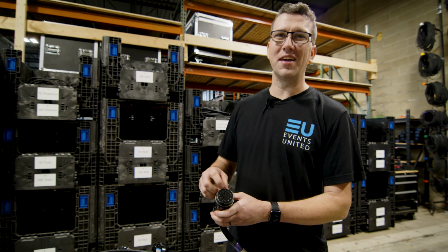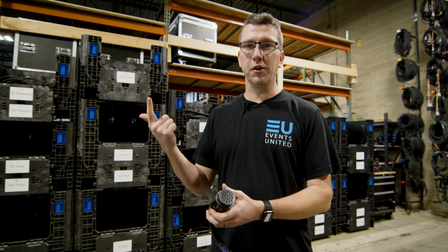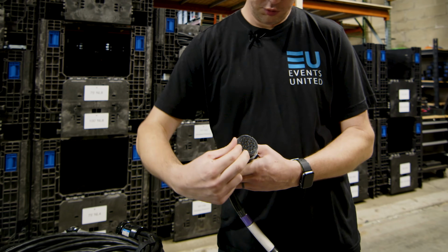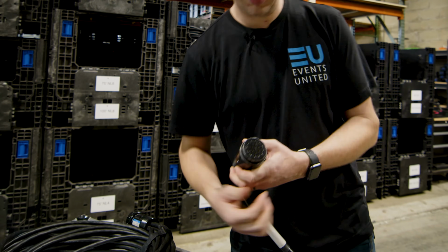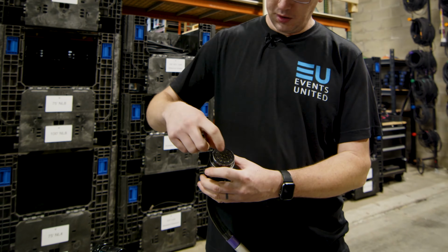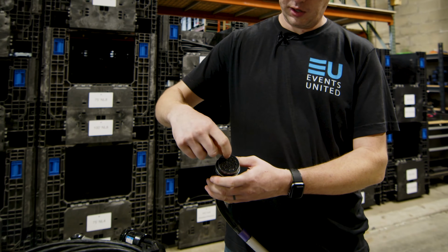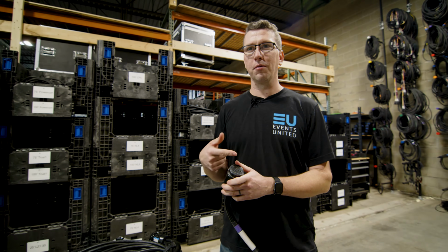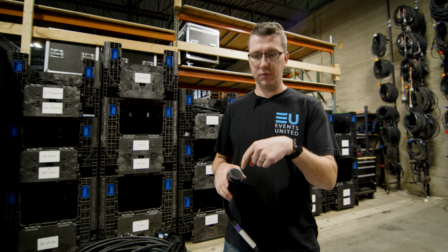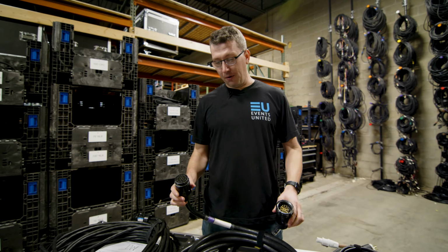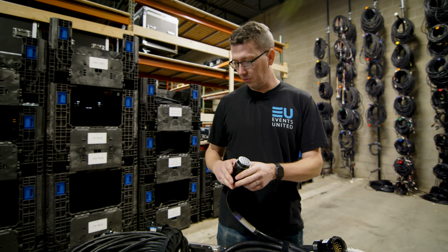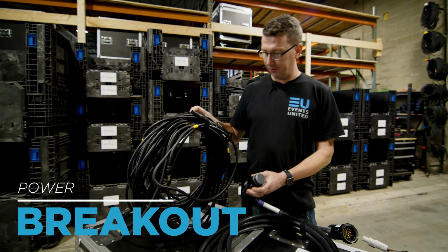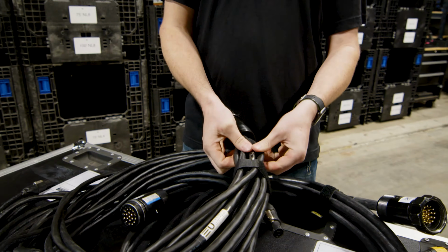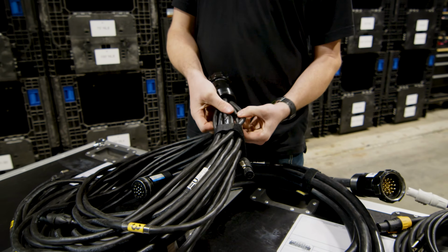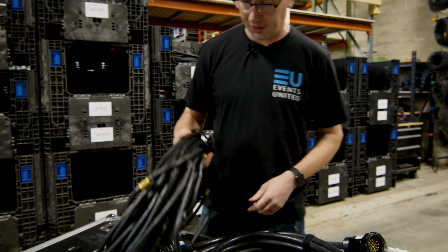Each one of these pins on the outer ring is a neutral and a hot. 1, 2, 3, 4, 5, 6 separate neutral and hot combinations. Then the center ring inside this connector joins all the pins, and the grounds get attached to those pins. But getting power from this to lighting fixtures, we use what's called a Socapex breakout. A Socapex connector on one end, you'll see 1, 2, 3, 4, 5, 6 individual cables coming out of that.